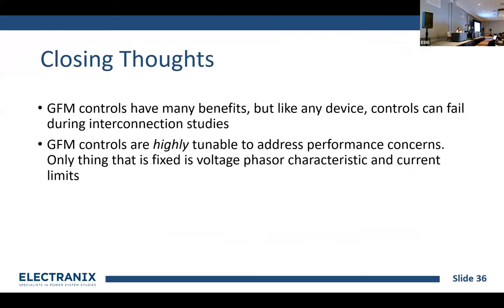A few closing thoughts: grid forming controls have lots of benefits, but like any device, controls can fail during interconnection studies — so we have to be careful about making these control changes. Grid forming controls are highly tunable — I showed you three different responses that look vastly different. I think there's a lot we can do with our controls to address performance concerns. The only constraints we have to work with are our definition of grid forming, the fixed voltage phasor we need, and our current limits. Within those parameters, there's a lot we can do.